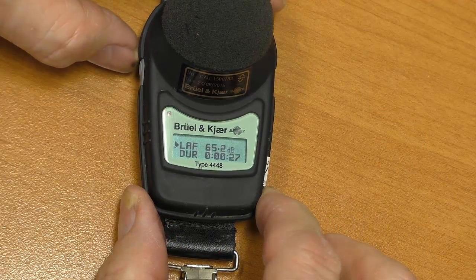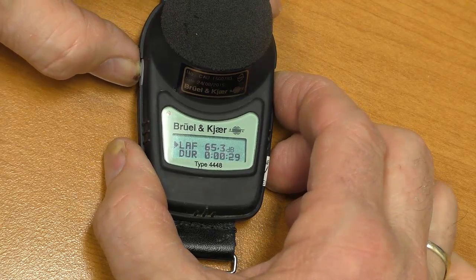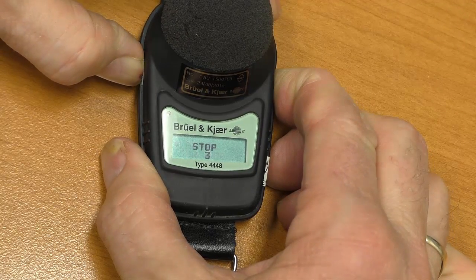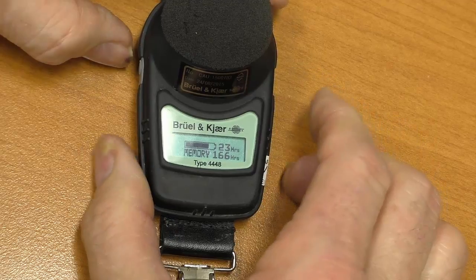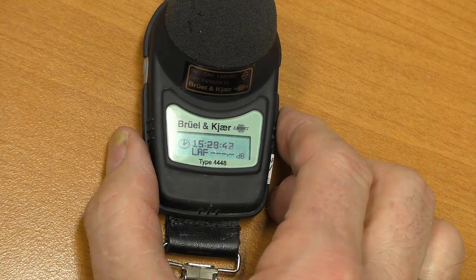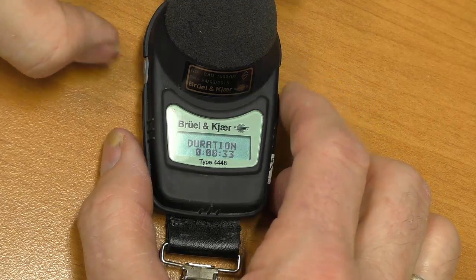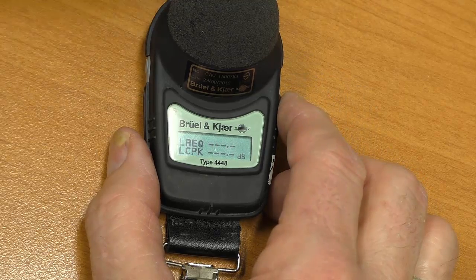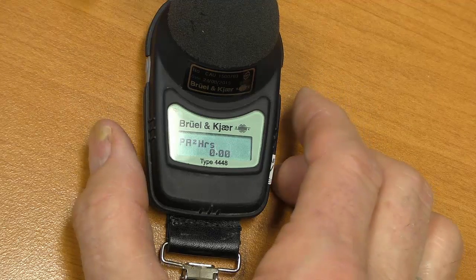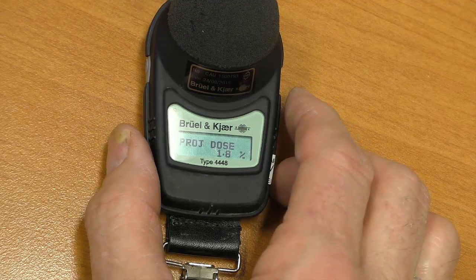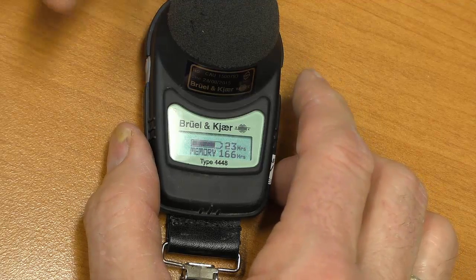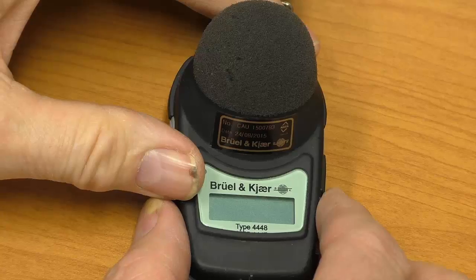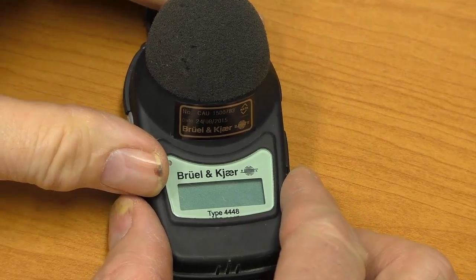Now when you want to stop logging, we push both keys in. There we have stopped. So to start, you push both keys in. To stop, you push both keys in. You can lock it by holding the right key and pushing three times, and unlock by holding the right key and pushing three times. The instrument must be calibrated prior to use, so we rotate the windshield and remove it.